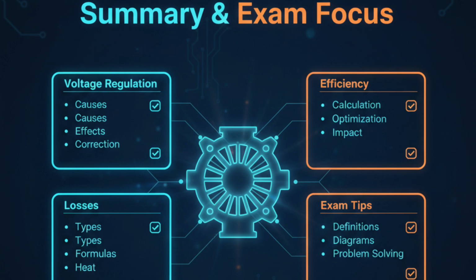Voltage regulation tells us how terminal voltage changes from no load to full load and is strongly influenced by power factor, armature reaction, and internal impedance. Alternator losses include copper, iron, mechanical, and stray losses, all of which reduce useful output power. Efficiency reaches its maximum near rated load, making proper generator loading essential in marine applications.